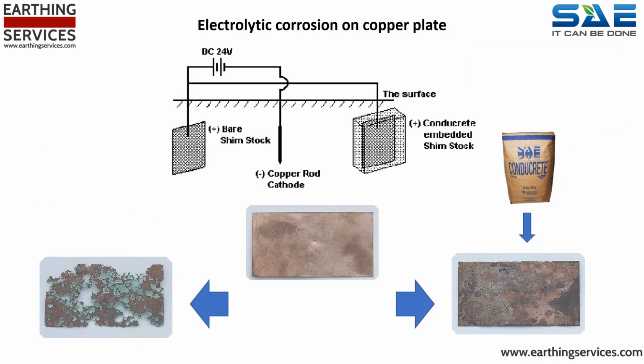Some companies do not use earth rods and instead use copper plates, lattice mats, or even bare cable. As copper is a non-ferrous metal, there is often a misunderstanding that it will not deteriorate. However, whenever there is an electrical discharge, there is electrolytic loss of the conductor.